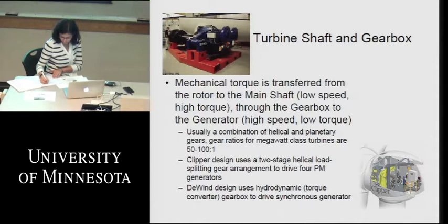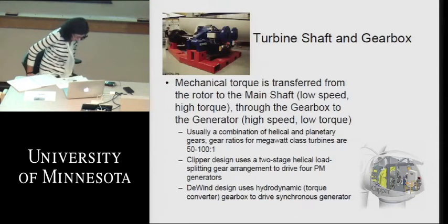You can see the second bullet. Clipper uses a different arrangement. It uses a 2-stage helical load splitting gear arrangement to drive 4 generators at once. They feel the advantage of this is that if one generator goes down, they could take it out for maintenance and operate with 3 generators or even 2. So if these were 750 kW generators in this Clipper machine and you took one out, instead of having 3 megawatts, you'd have 2.25, and you could operate that way until you replace that other generator. It's a design decision that you take from the beginning, but this is the tactic Clipper chose to use.